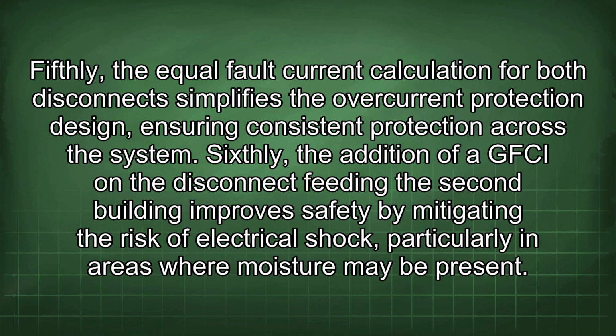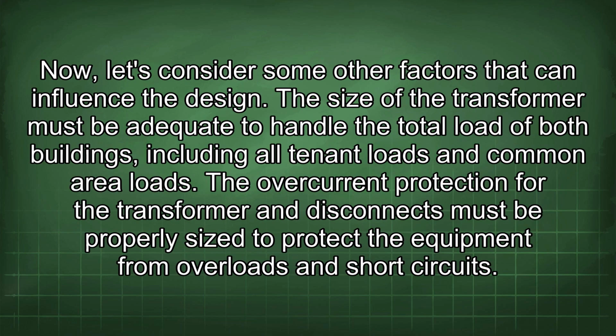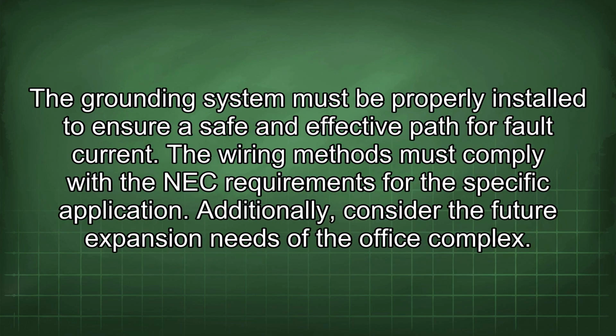Sixthly, the addition of a GFCI on the disconnect feeding the second building improves safety by mitigating the risk of electrical shock, particularly in areas where moisture may be present. Now, let's consider some other factors that can influence the design. The size of the transformer must be adequate to handle the total load of both buildings, including all tenant loads and common area loads. The overcurrent protection for the transformer and disconnects must be properly sized to protect the equipment from overloads and short circuits. The grounding system must be properly installed to ensure a safe and effective path for fault current. The wiring methods must comply with the NEC requirements for the specific application.